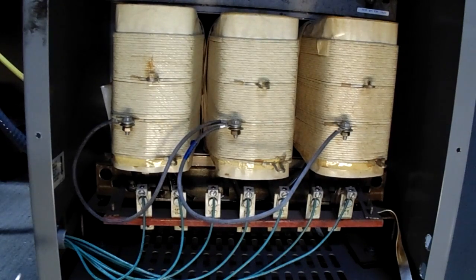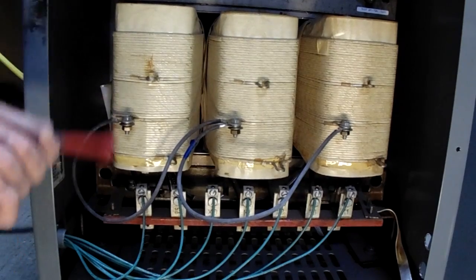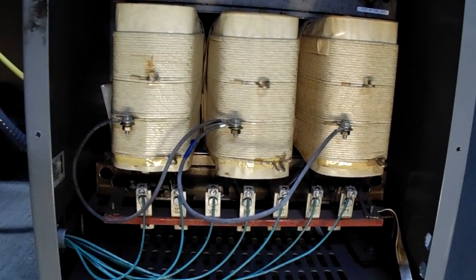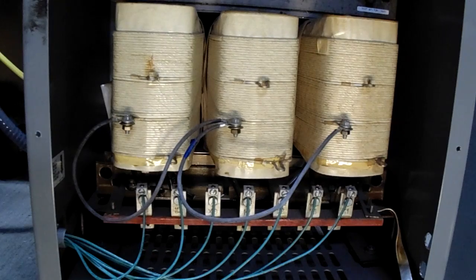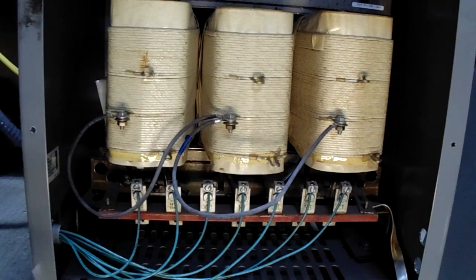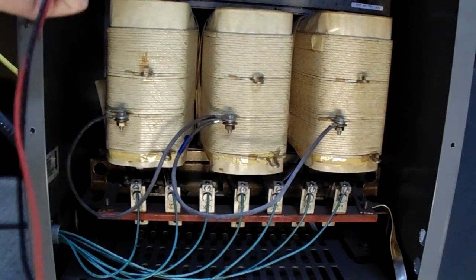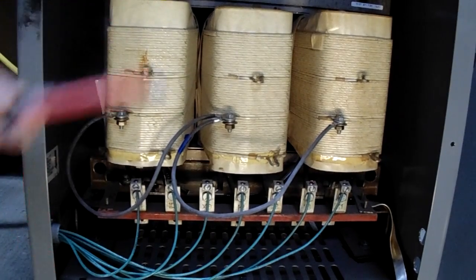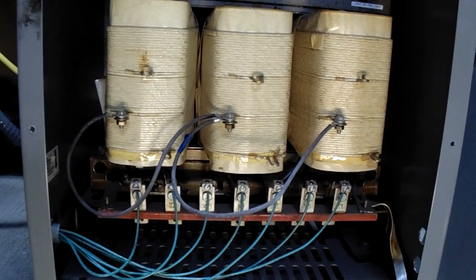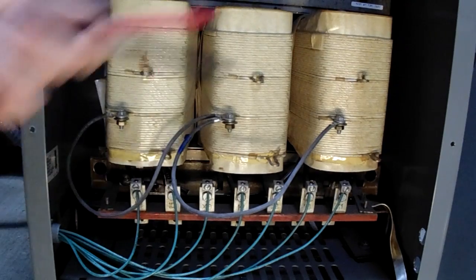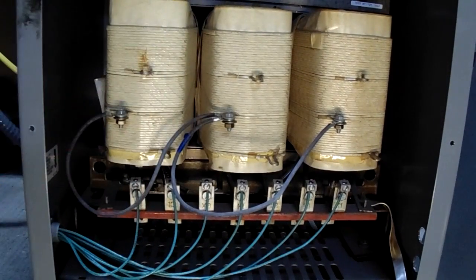And most of the time, if you're getting a really odd voltage just by a leg sitting over here not doing anything, or a phase sitting over here not doing anything, then you probably won't be able to put a load on it. So if you are getting a really odd voltage, you probably won't be able to power anything off that leg because there is no primary active in that leg, so obviously the secondary is not going to be doing anything either, except maybe just sitting there and acquiring some power from another coil or winding.